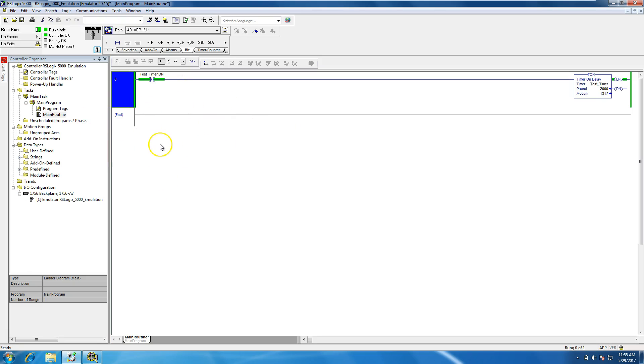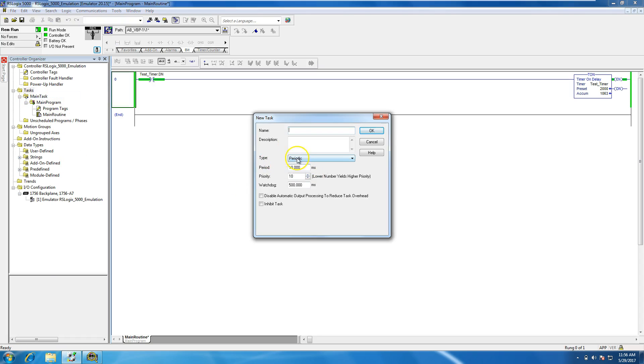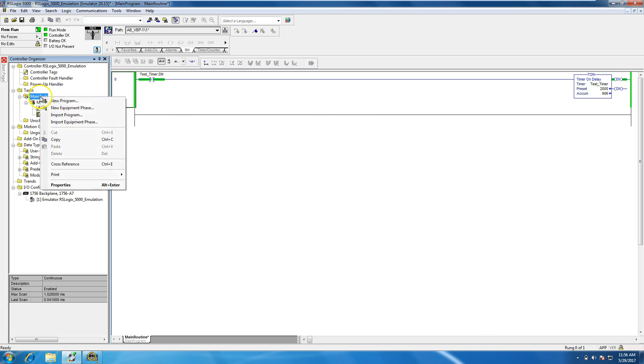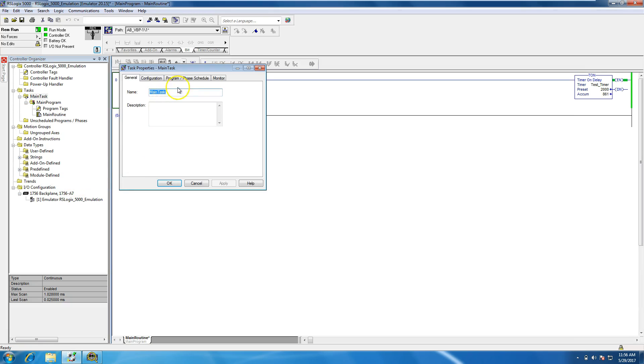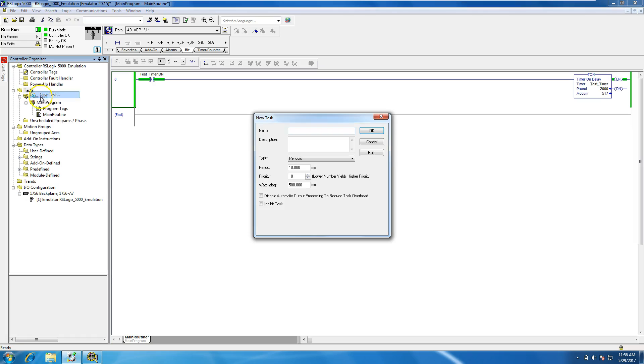And this is basically how to initially set up a program. Now what you can do, preferably I like to add periodic tasks instead of the continuous task. If you look at this task right here, it is a continuous task, which basically can be done for small applications, but you really don't have any time and control. You're basically at the mercy of your processor. So what I like to do is add periodic tasks.